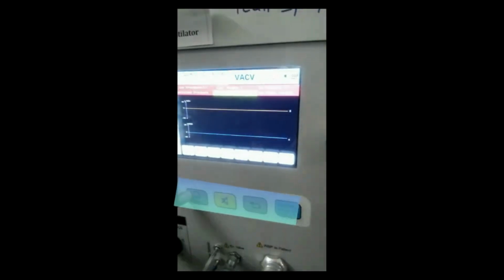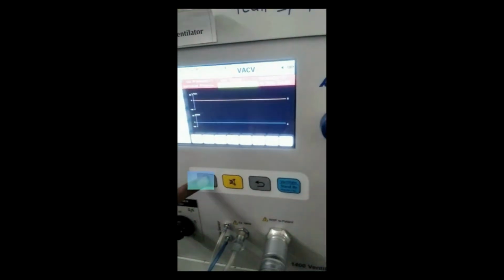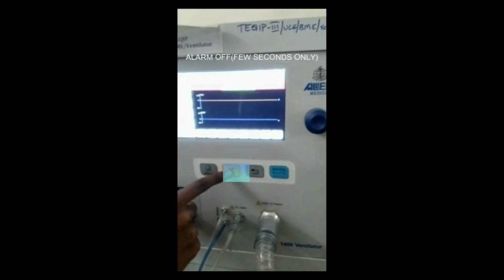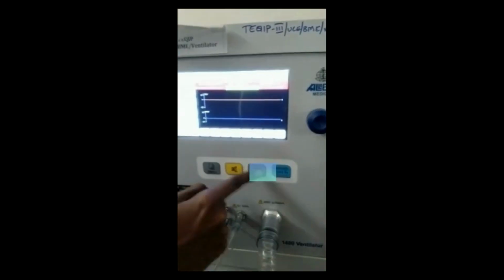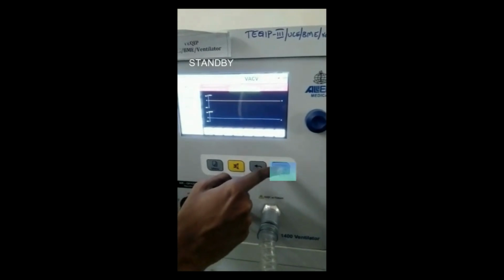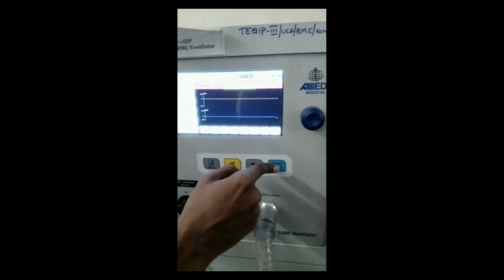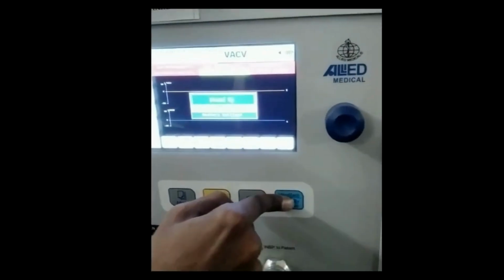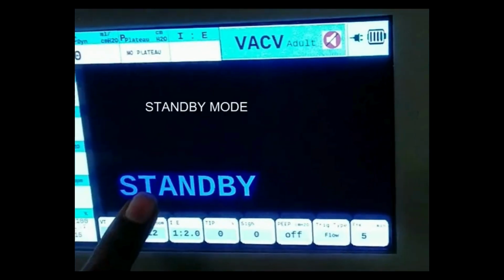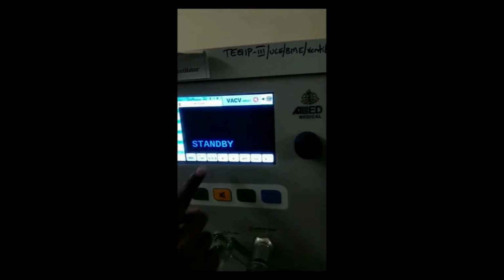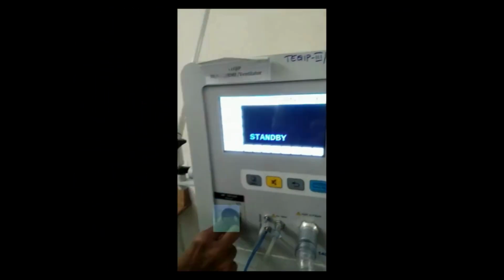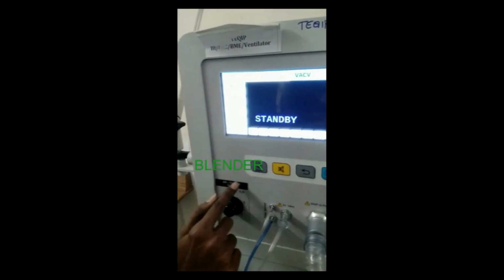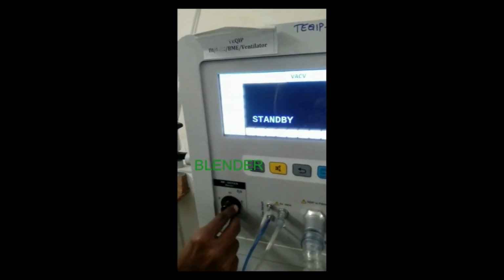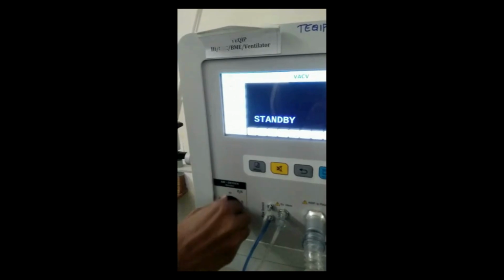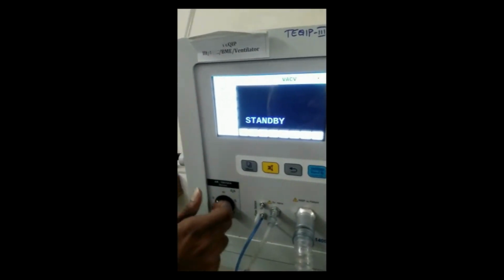And these are all the buttons. This is the menu button, this is the alarm off button, and this is a back button, and this button is used to go to the standby mode. If I press this button for 2 to 3 seconds, it will simply go to standby. And here you can see there is a knob, also known as a blender. If we set this blender to 40%, it means we are sending 40% oxygen to the patient.